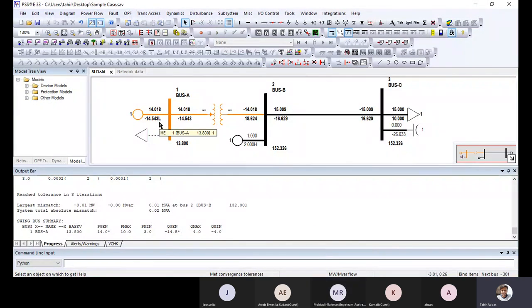If you run that generator under the excitation limit for the next 2 to 3 hours, the generator will lose synchronism. That is a loss of synchronism, that is loss of the generator. The generator will trip. So this is the under excitation limit and the over excitation limit.